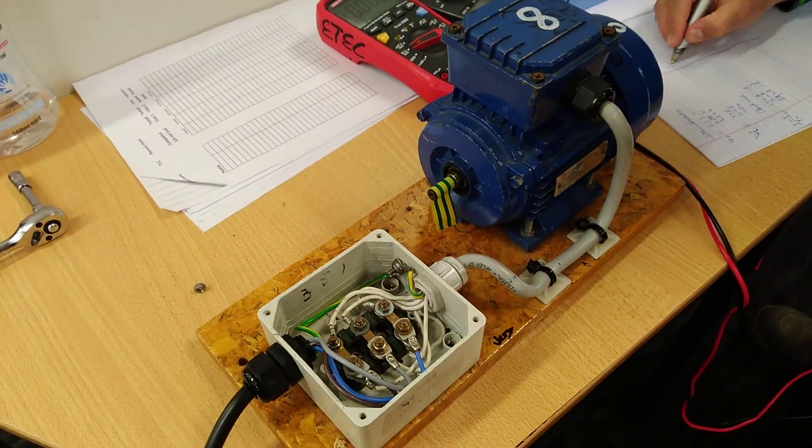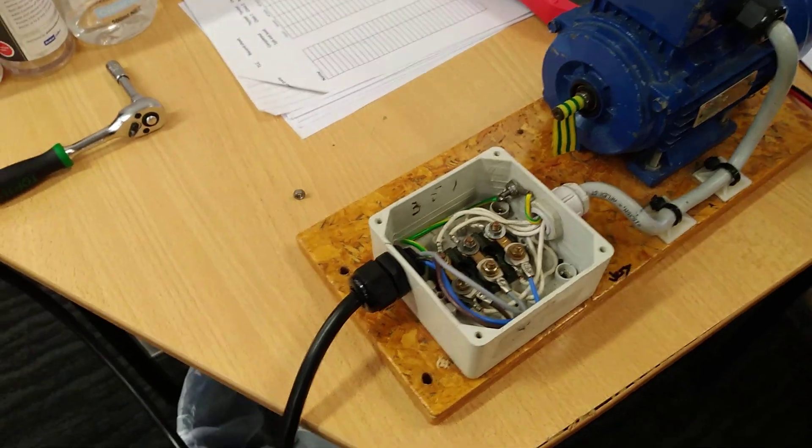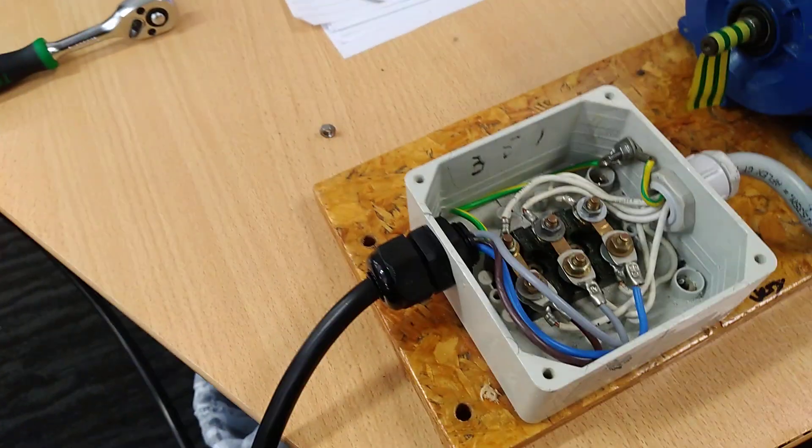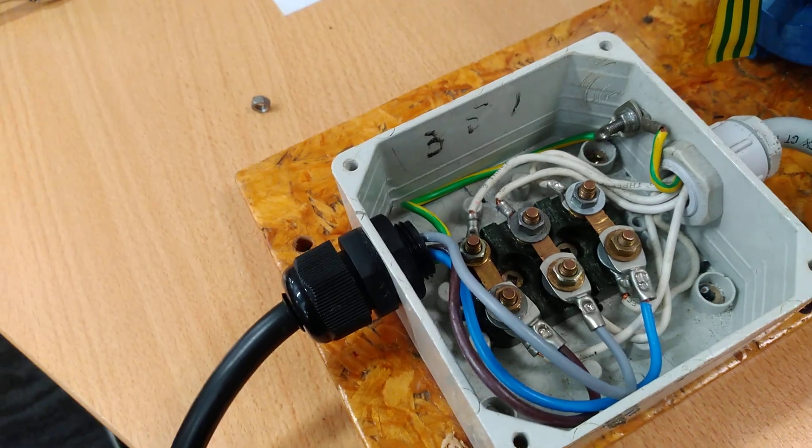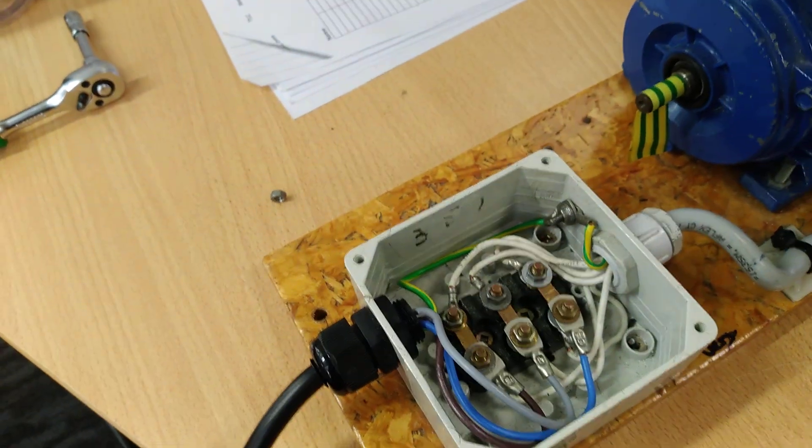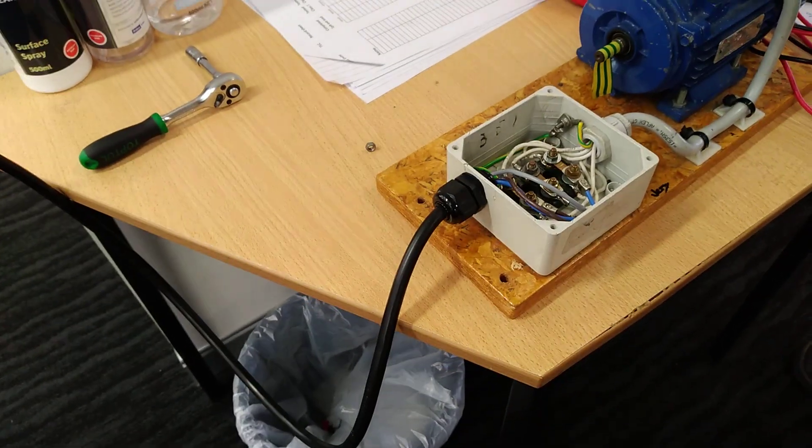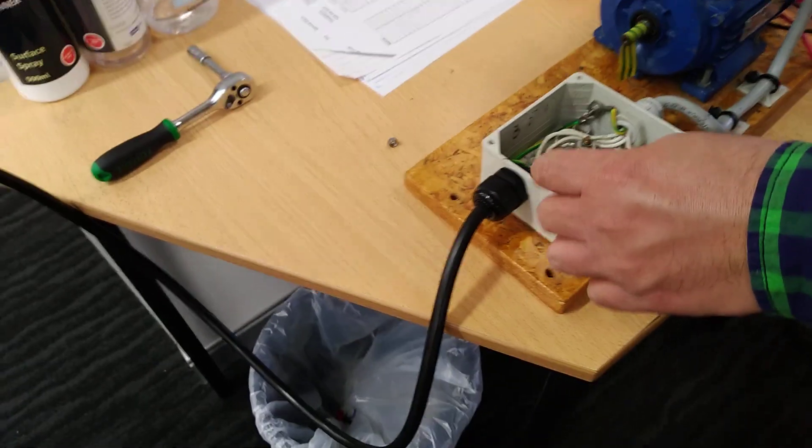Now we'll do the currents. Unfortunately we can only really measure the line current, because that's where we're going to be putting the clamp tester around. We can calculate the phase current though by root 3 if we like. So I'll get you to put your clamp tester around, and then we'll put the power on after you've got the clamp tester in place.